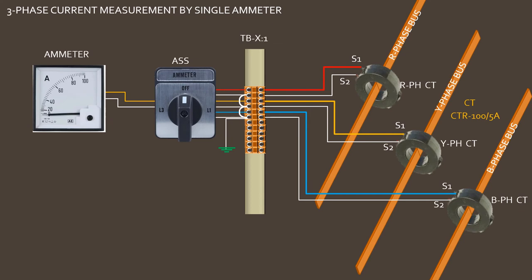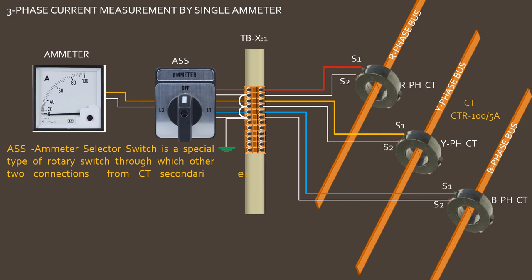By using an ampere selector switch, three phase readings can be obtained by a single ammeter. ASS ampere selector switch is a special type of rotary switch through which the other two connections of CT secondaries become shorted at the switch.